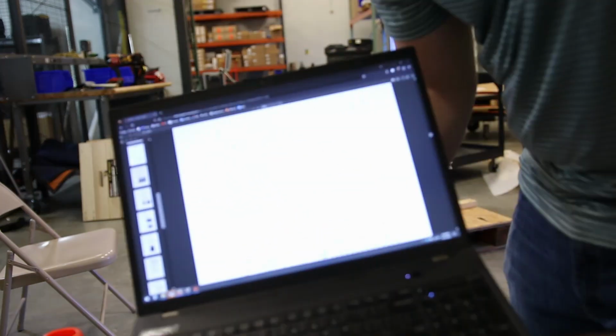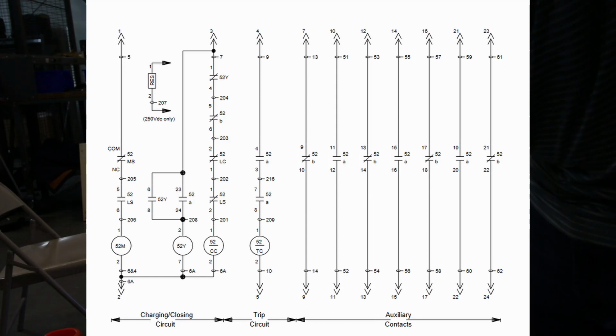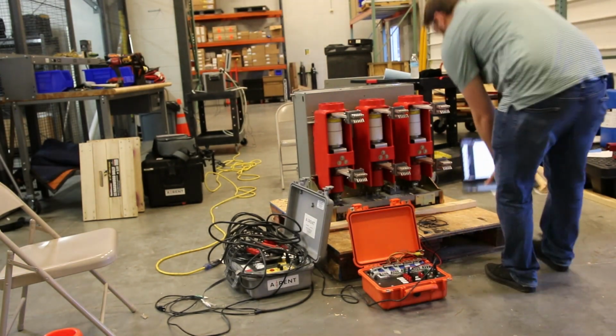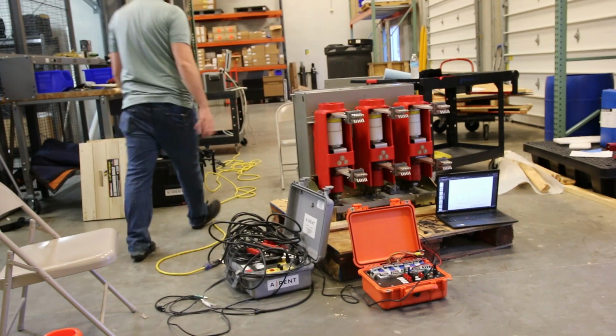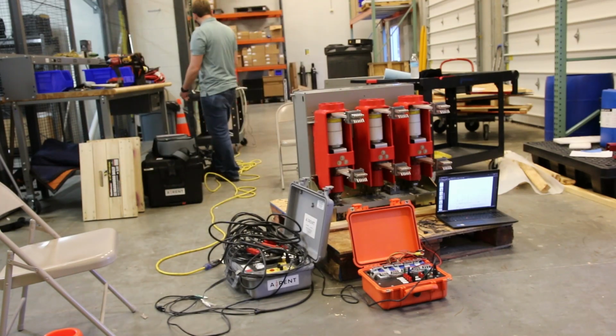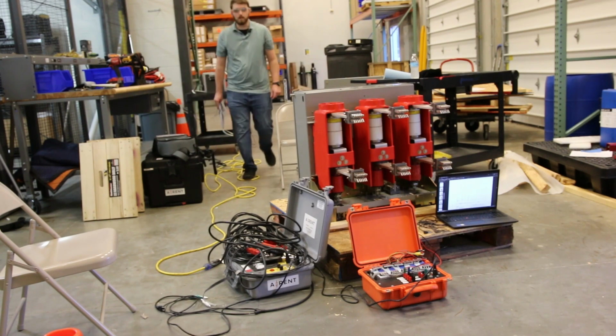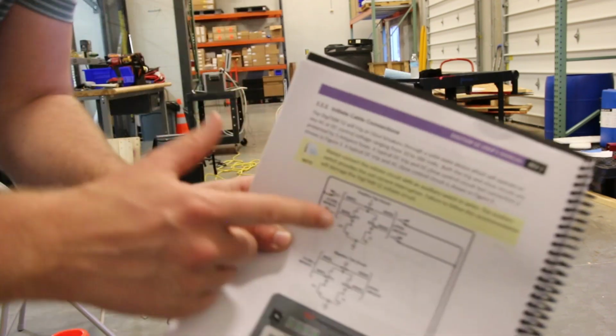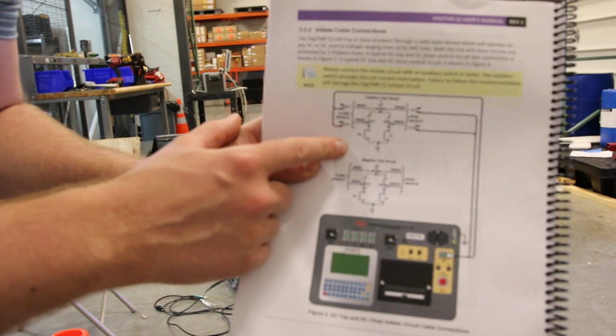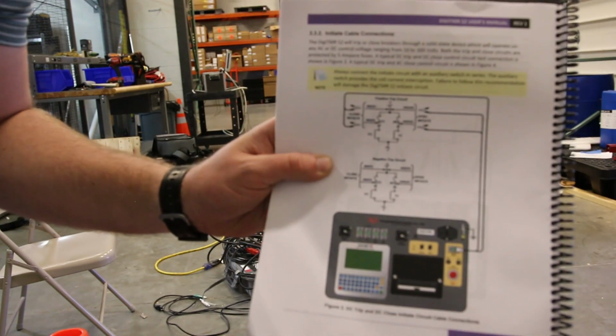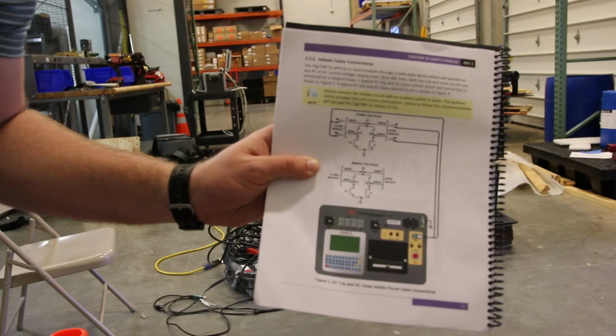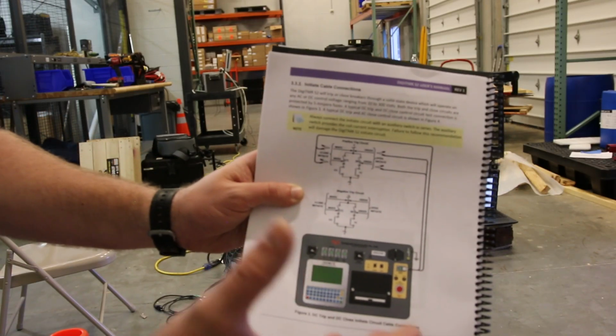So I've got my drawing, which is not going to be exposed right or in focus. We've got the manual open with the pinout of the secondary. We're going to reference this, and then we're also going to reference the drawing from the manual from our test set, because that is going to tell us how the test set needs to cut in between the open and closed circuits. So every test set is going to be different, every breaker is going to be different, but this should show you vaguely how to hook it up, and you just sort of have to interpret how to combine those things.